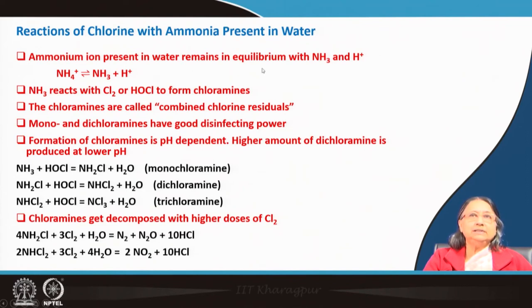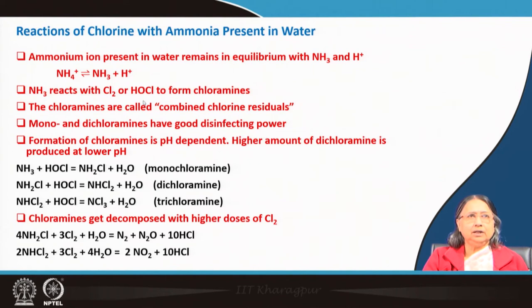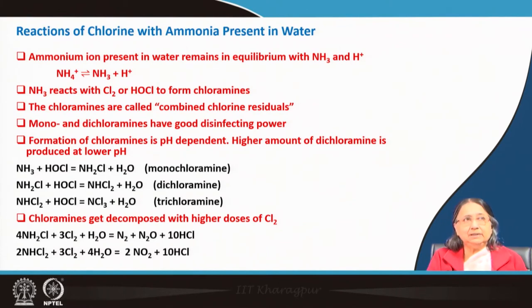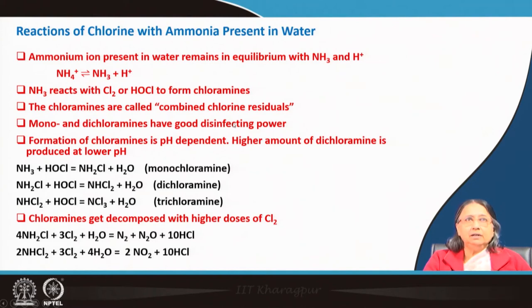Ammonium ion present in water remains in equilibrium with ammonia and H⁺. NH₃ reacts with chlorine or HOCl to form chloramines. The chloramines are called combined chlorine residuals, whereas HOCl, OCl⁻, and Cl₂ are called free chlorine residuals. Mono- and dichloramines also have good disinfecting properties, but not as good as free chlorine residuals — they are weaker, but still have disinfecting power.